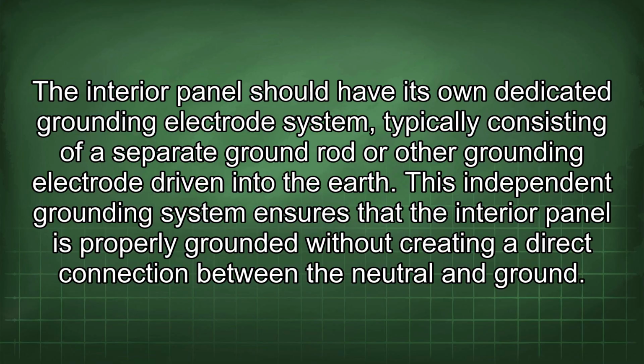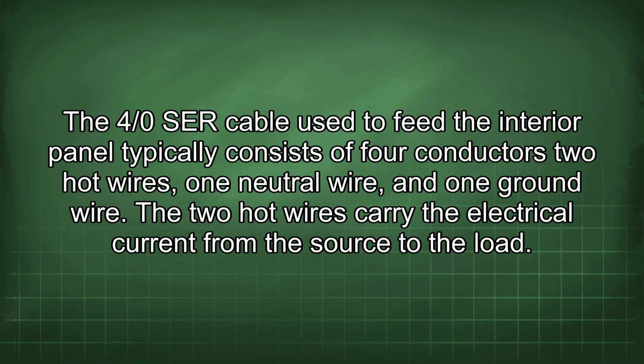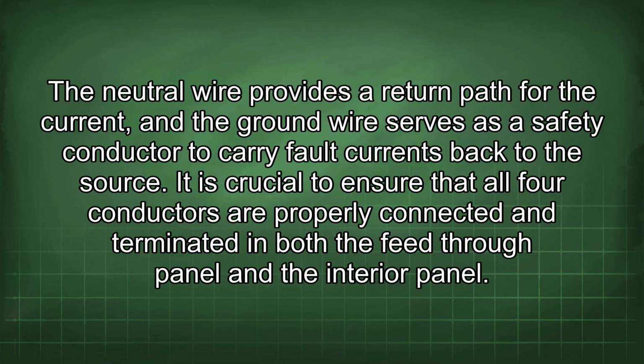and ground. The 4/0 SER cable used to feed the interior panel typically consists of 4 conductors: 2 hot wires, 1 neutral wire, and 1 ground wire. The 2 hot wires carry the electrical current from the source to the load. The neutral wire provides a return path for the current, and the ground wire serves as a safety conductor to carry fault currents back to the source.